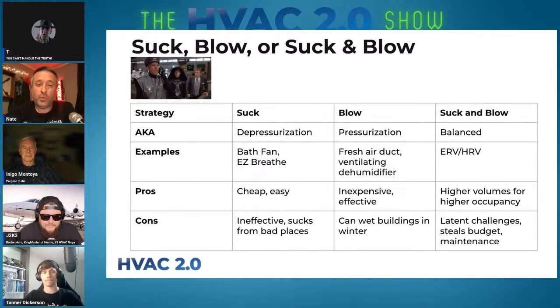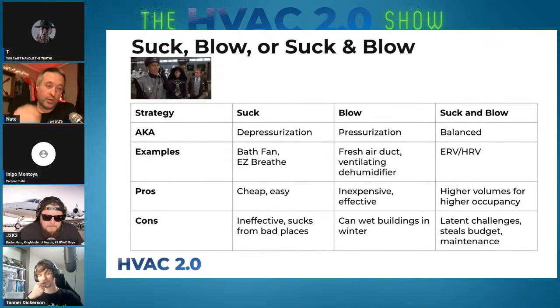This is how we learned to not like ERVs. We put one in a client's home and could not control the humidity in that house - it went totally out of control. I had to turn down the speed, and sometimes we had to turn it off just to get control. ERVs do not dehumidify; they only reduce how much they add. So you're still adding latent load that you have to deal with.